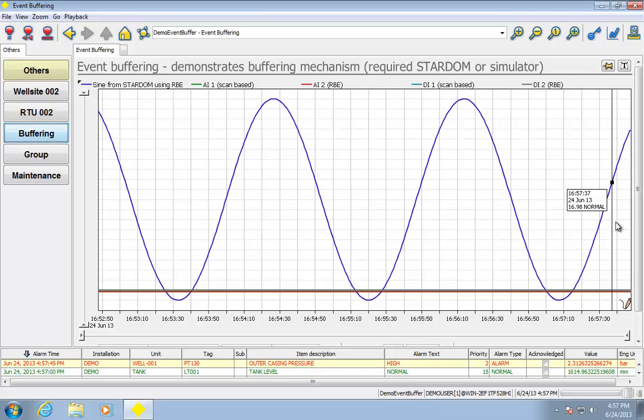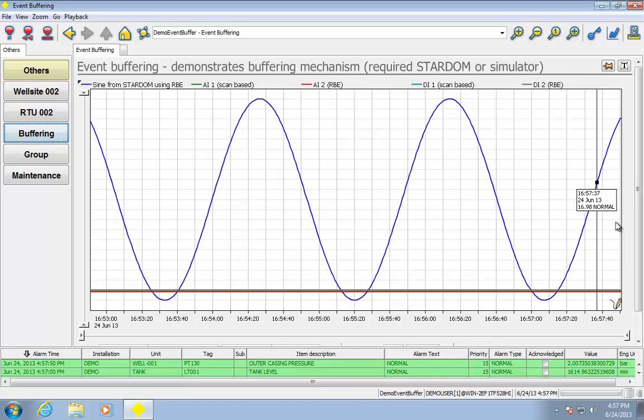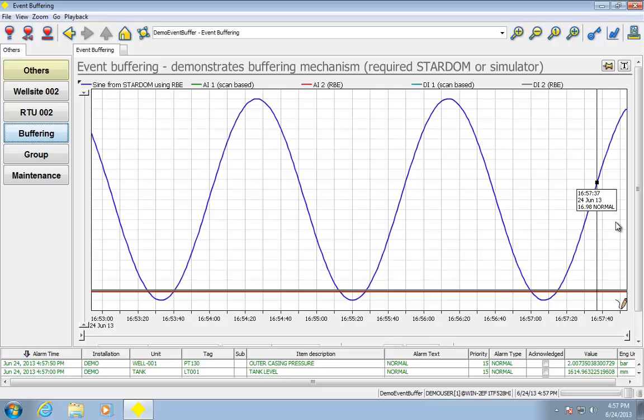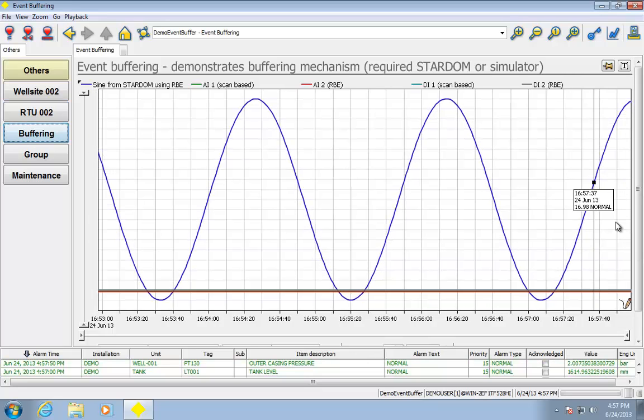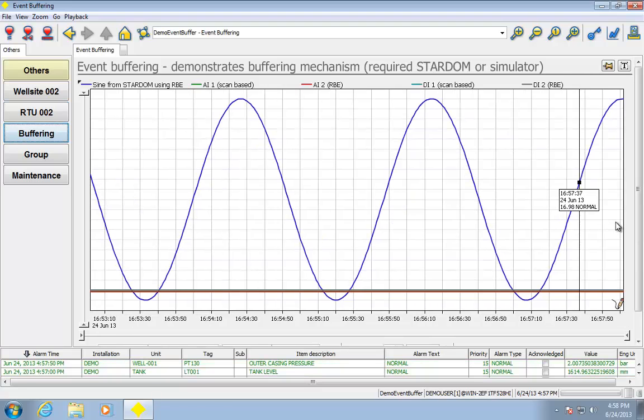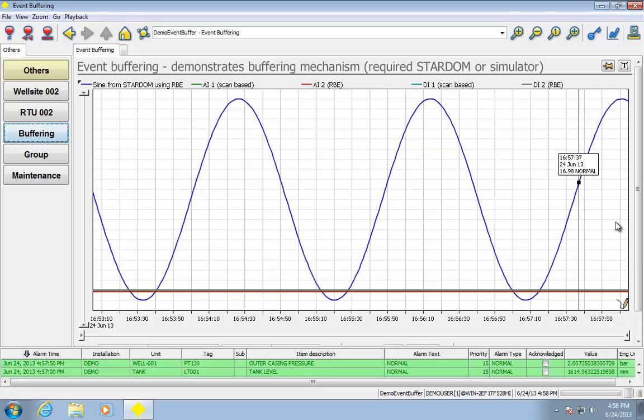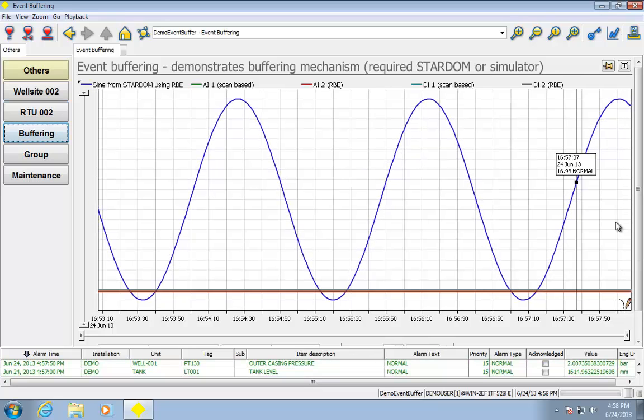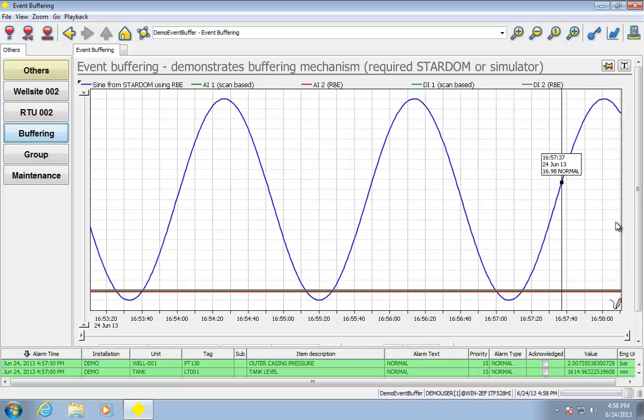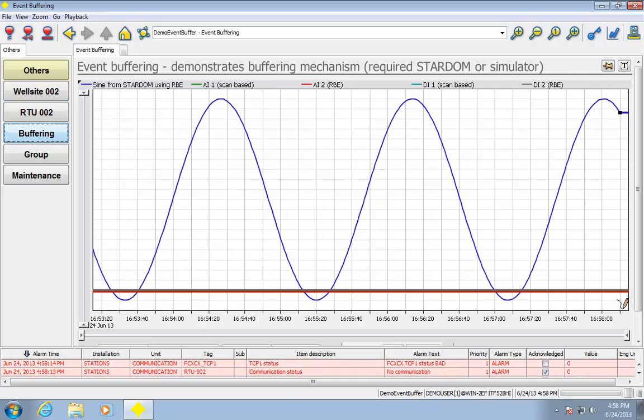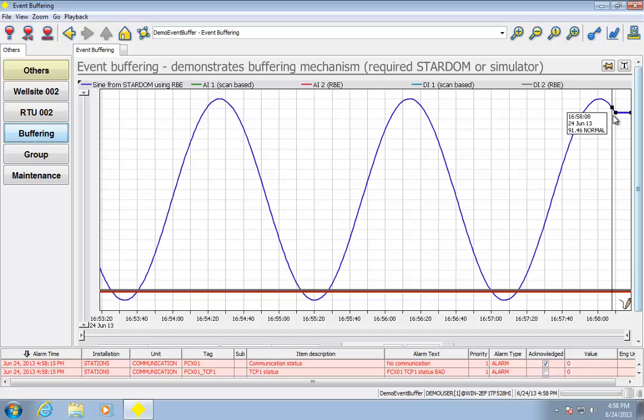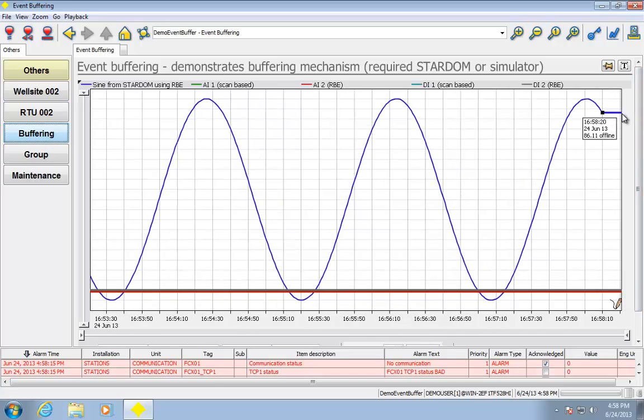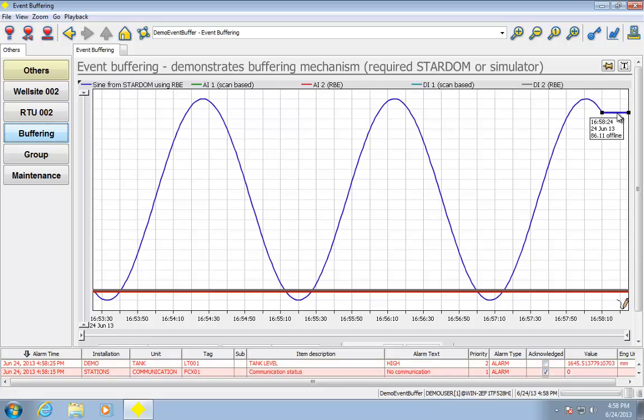So when you combine the Stardom process automation controller or Stardom RTU with FastTools, we get something called event buffering. And what this means is we won't lose any data if the PC goes down, we won't lose any data if the network connection goes down. So what I'm going to do right now is simulate a network disconnection by actually going to the controller and disconnecting the Ethernet cable.